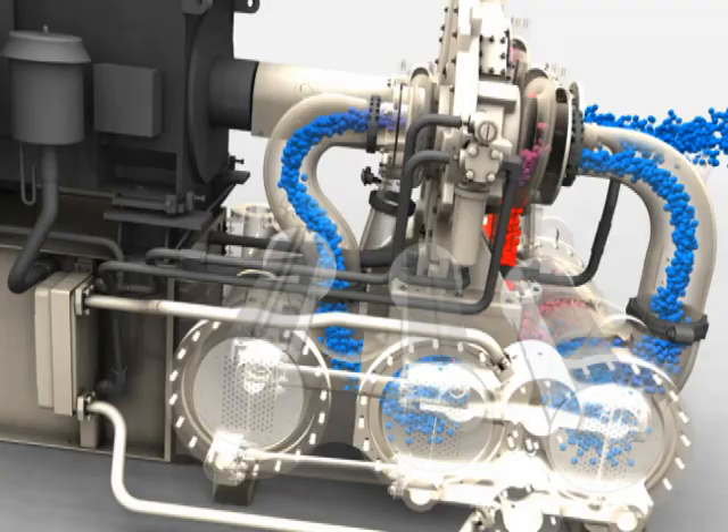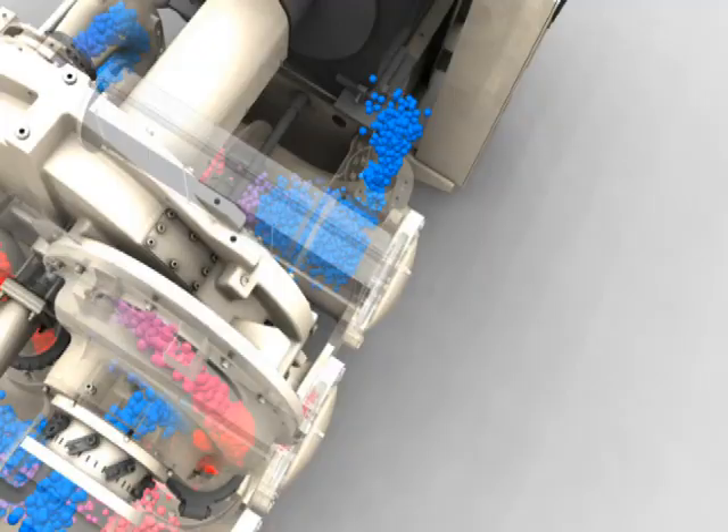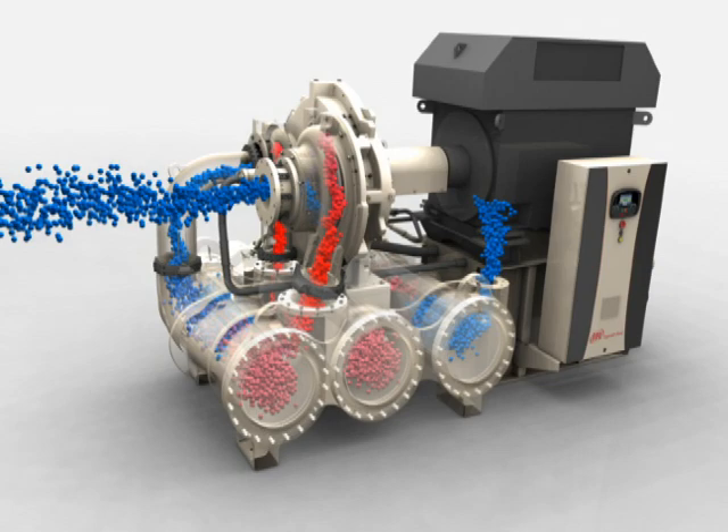Water flows through the extended surface-style tubes, which effectively reduce the air temperature to as low as 5 degrees Celsius or 9 degrees Fahrenheit above the inlet water temperature. The generously sized coolers have an ultra-low pressure drop, further reducing power consumption. The resulting condensate is separated out and sent to air-saving no-loss moisture traps, maximizing efficiency.